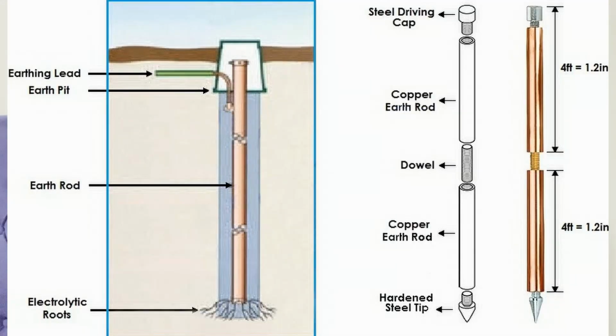Now, there are various sources of power in your home: various metallic elements, and for those of you who have a generator, that's a source of power too, which has to have its own earth connection. The AC mains coming in has to have its own earth - that's the TT system I talked about, the own rod in the ground. You have to bond all the metallic parts in your structure - the rebar, metallic balustrades if you have them - and even the lightning protection system has to be bonded to earth. So if you're going to have a standby generator, make sure it has its own independent earth rod next to it - very important.